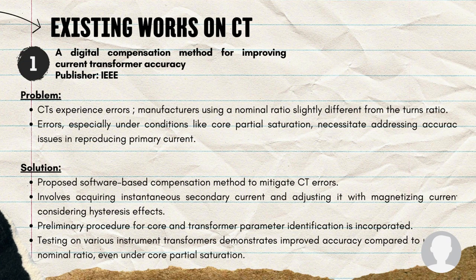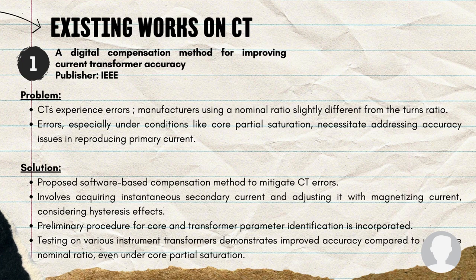A problem and solution identified from the research: CTs experience errors despite manufacturers using a nominal ratio slightly different from the turns ratio — errors especially under conditions like core partial saturation and in reproducing primary current. The proposed solution is a software-based compensation method to mitigate CT errors. It involves acquiring instantaneous secondary current and adjusting it with magnetizing current, considering hysteresis effects.